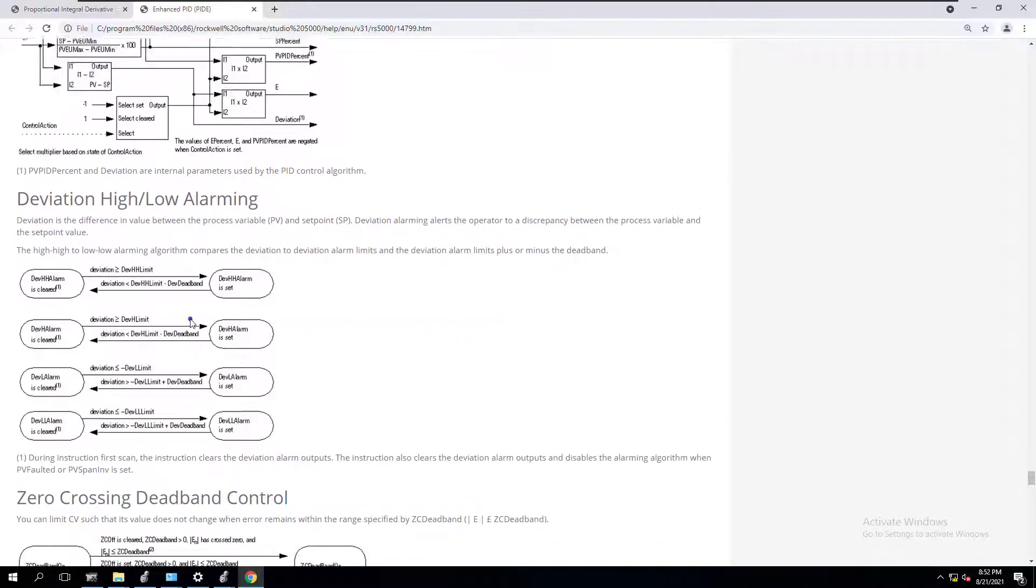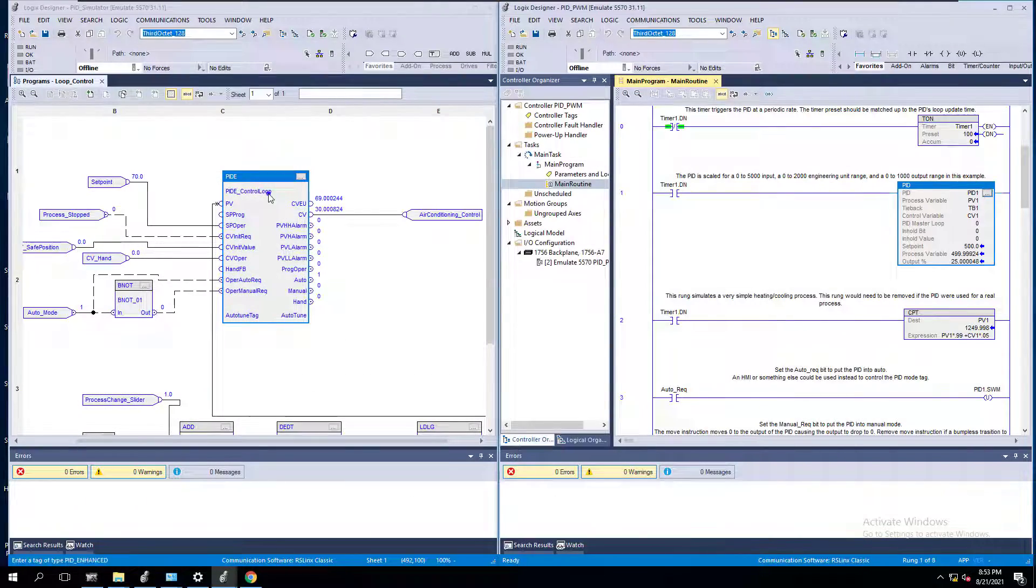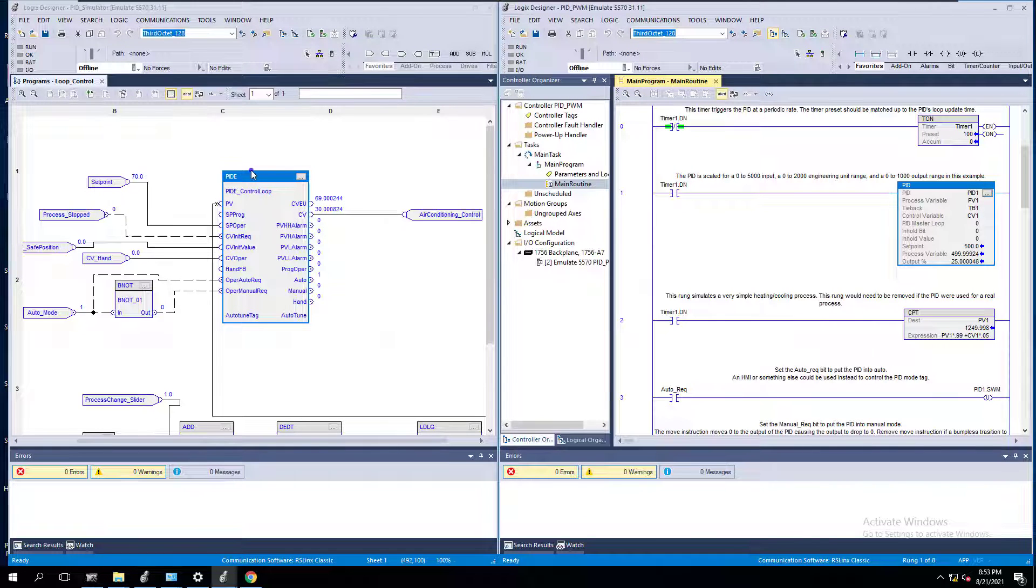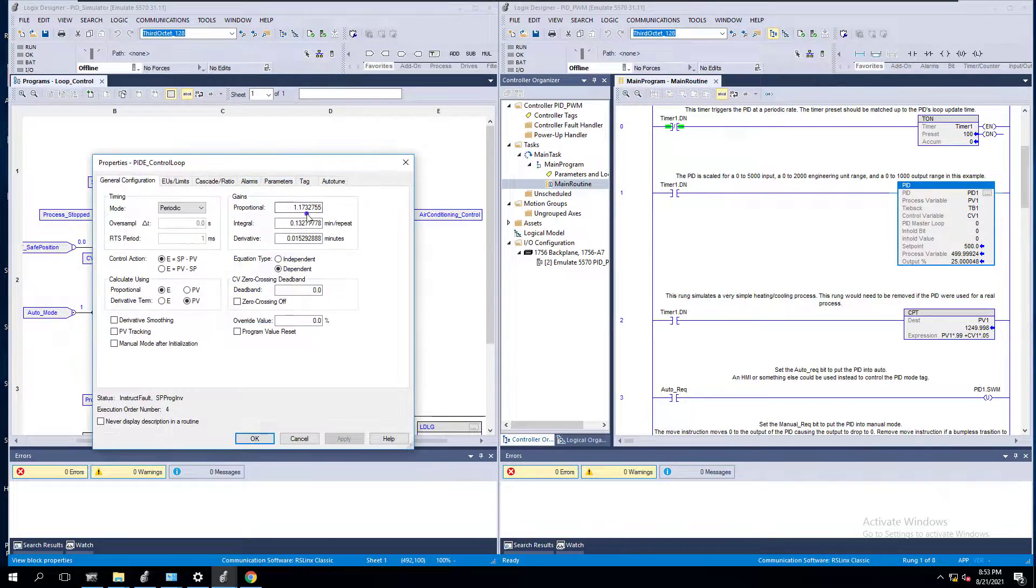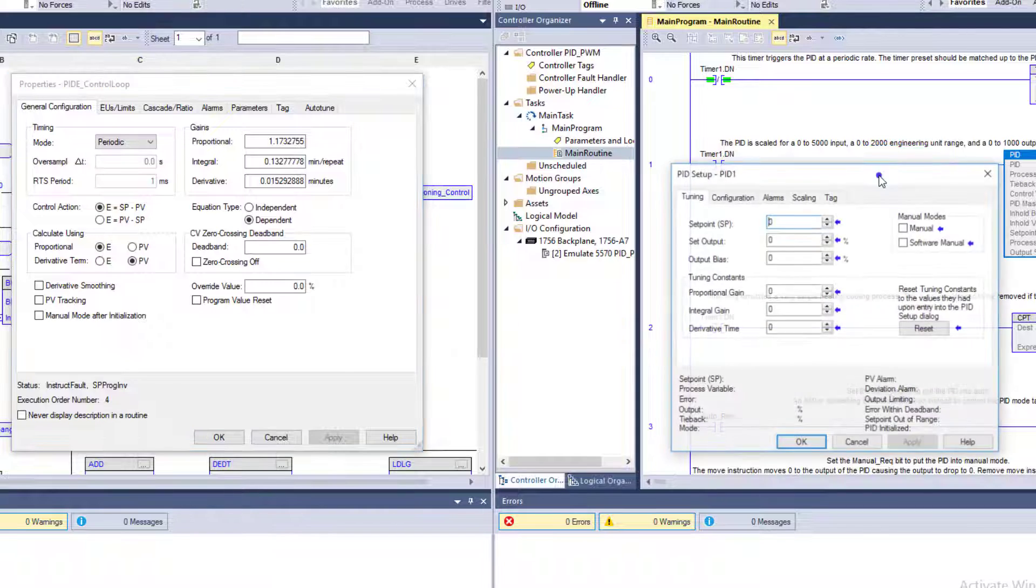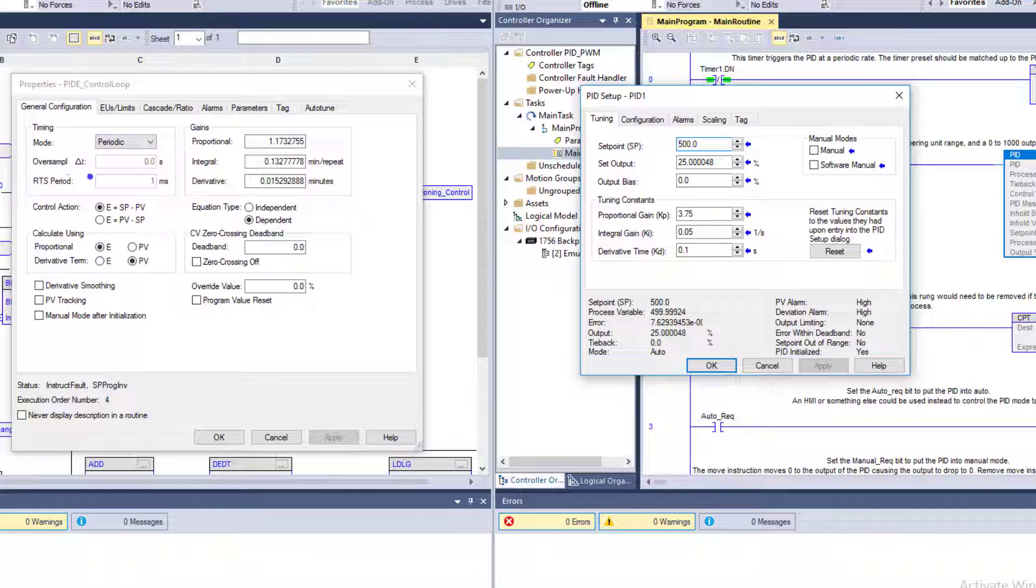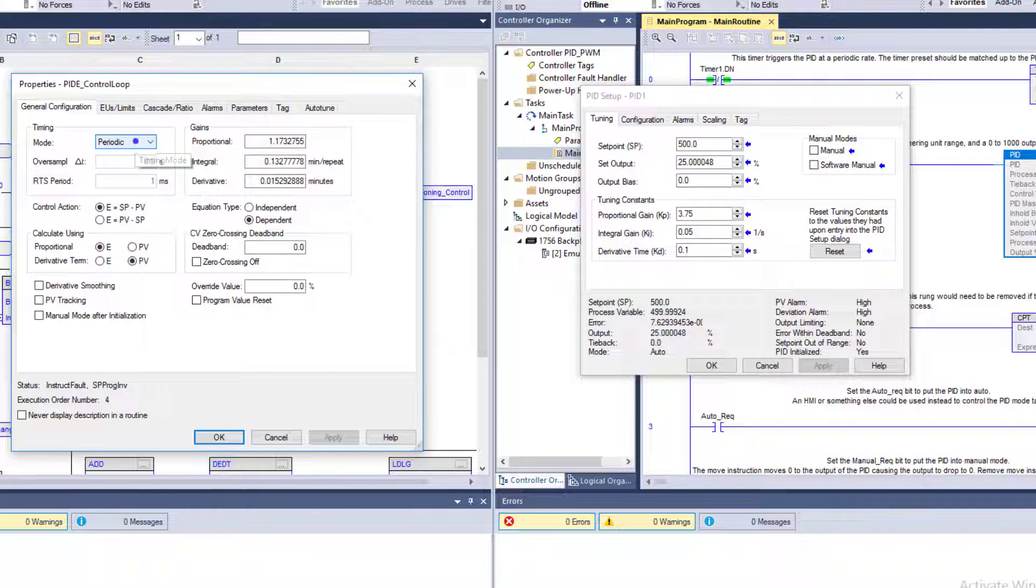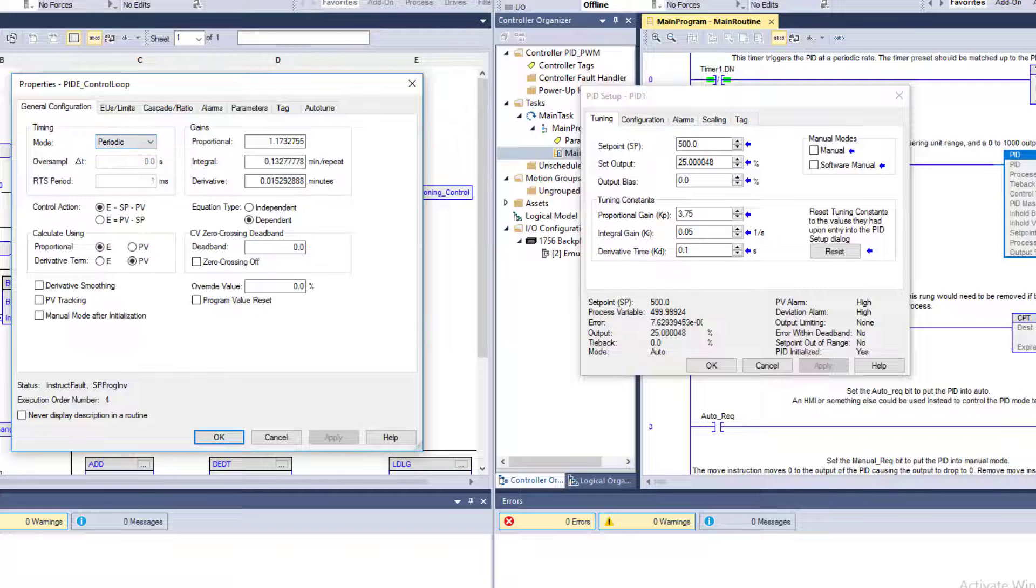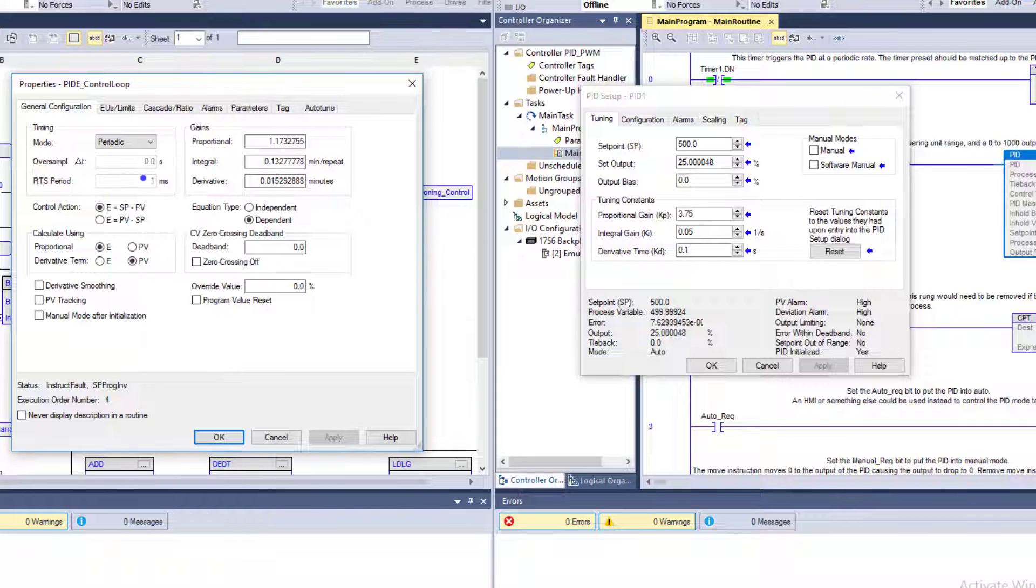A lot more detail goes into the PIDE. Let's actually look at the PIDE inside of the Studio 5000 environment. So you do have an auto-tune here. When it comes down to it, you have your timing mode, which is going to be a major difference. Your timing mode is really impacted by your timing and using it in the PIDE. You can have a periodic, which is going to be off your actual task rate of however you have your task rate. I recommend it always be periodic if you're going to use a PIDE.